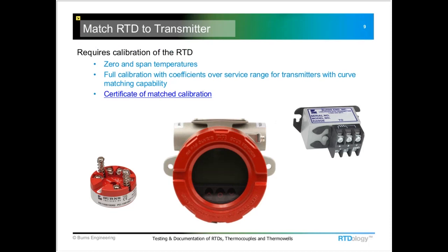And these coefficients are used in an interpolation equation, which some transmitters have the capability for. When you input those coefficients, they have all the math built in, and so it can actually interpolate between the actual calibration points and give you a much more accurate temperature measurement than you can by using just a probe that has not been calibrated. Otherwise, you'd have to look at those interchangeability numbers as essentially your accuracy of the probe at those temperatures. Doing this eliminates all that.